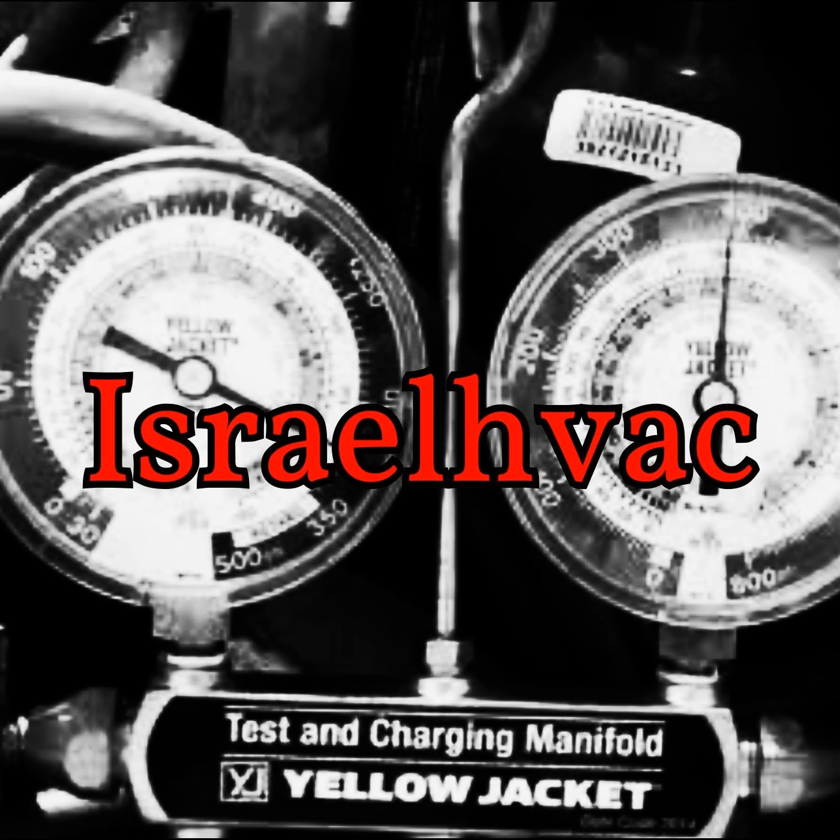Anything above single stage. I have a zone system, and the reason I wanted to stay with the 2-stage system is because then I can throw in a new Honeywell zone board, and I can stage my zones based off the percentage of zones. You can go into the settings there, so if just one floor is calling, then just first stage comes on. If both floors call, then the zone board will kick in second stage, and now you can cool upstairs and downstairs at the same time.